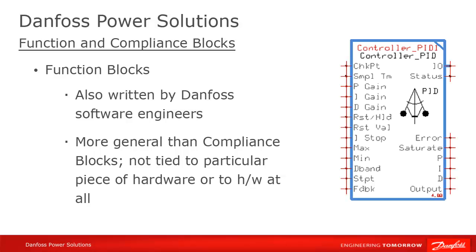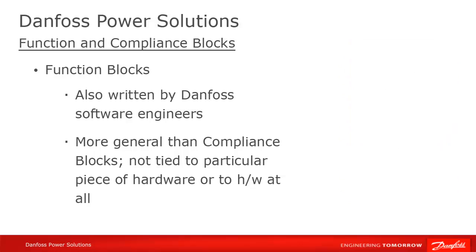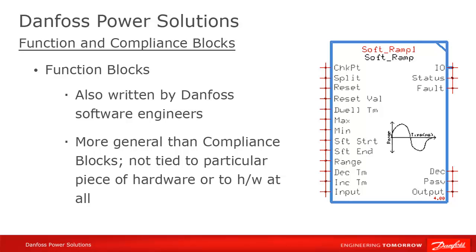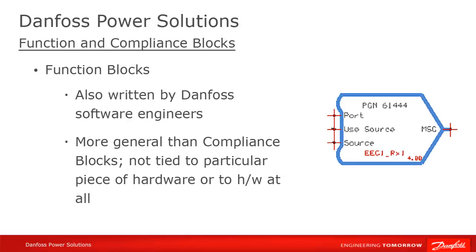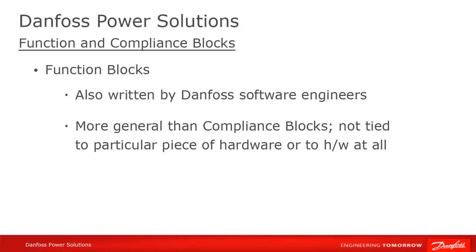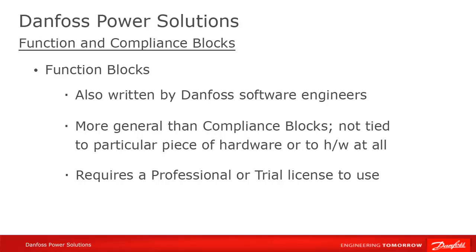There are other function blocks that aren't tied to hardware at all, like a PID block, a soft ramp block, or a J1939 CAN message block. Another major difference from a commercial perspective is that the use of function blocks requires a professional or a trial license. If you don't have one of those licenses activated, you will not be able to add a function block to your program.